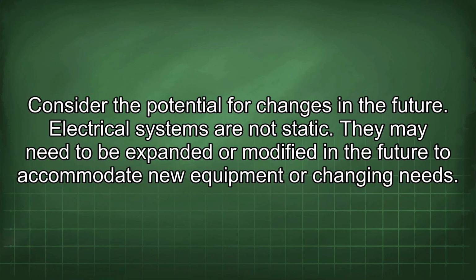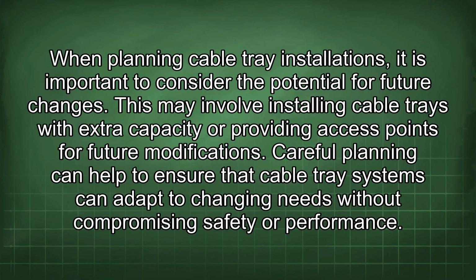Consider the potential for changes in the future. Electrical systems are not static. They may need to be expanded or modified in the future to accommodate new equipment or changing needs. When planning cable tray installations, it is important to consider the potential for future changes. This may involve installing cable trays with extra capacity or providing access points for future modifications. Careful planning can help to ensure that cable tray systems can adapt to changing needs without compromising safety or performance.